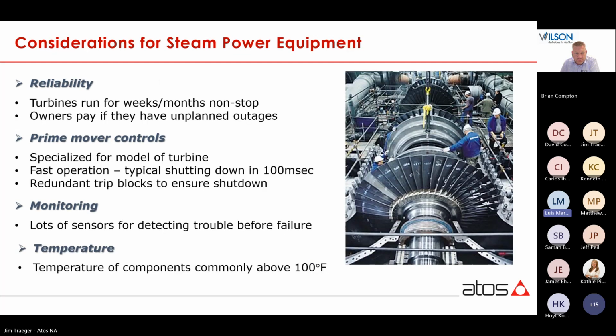Considerations for steam power equipment. Reliability is very important. Turbines run for weeks, months, non-stop, and sometimes owners pay if they have unplanned outages. Prime mover controls are required to be specialized for the model of the turbine. They have fast operation. Typical shutdown is around 100 milliseconds. Also, there are redundant hydraulic trip blocks to ensure shutdown. Monitoring: lots of sensors for detecting trouble before failure. And temperatures of components on these hydraulic systems are commonly above 100 degrees Fahrenheit. So here's a picture of a turbine under service. Next slide.